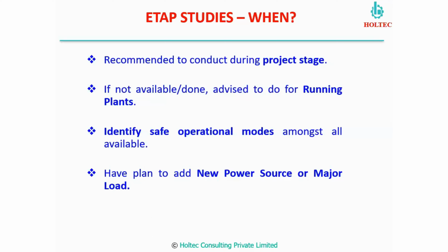If you want to identify the safe operational modes for operation of a plant, in our power distribution system we have tie feeders, bus couplers, and so many flexibilities we are keeping. So we have different operational scenarios which we can create in our power distribution system. Here in ETAP, without doing any online analysis, we can do it offline. We can create all possible operational scenarios and check the performance of the short circuit currents.